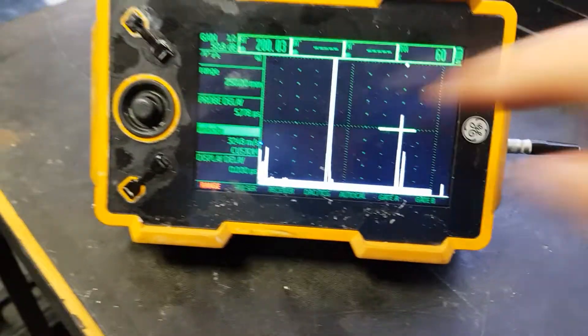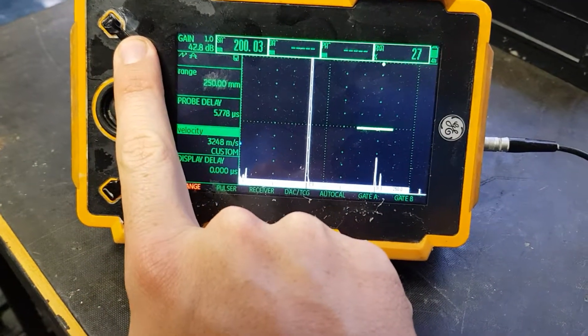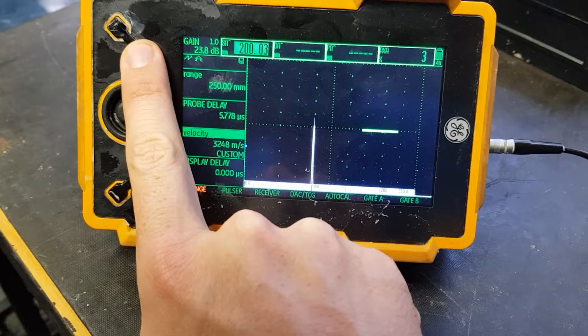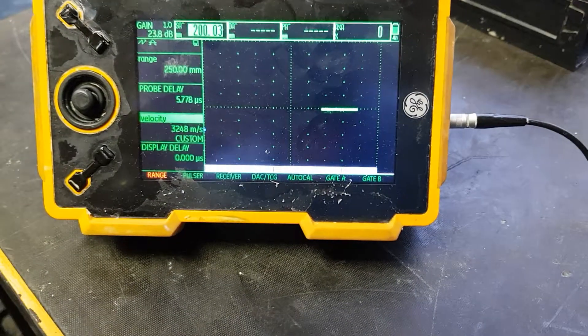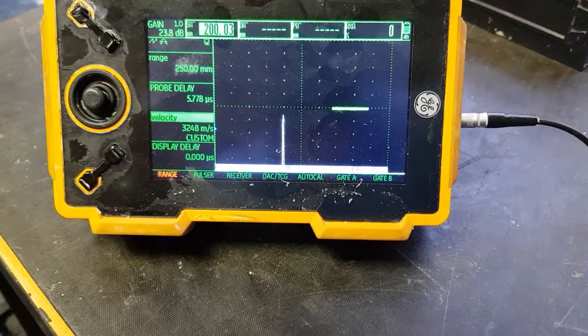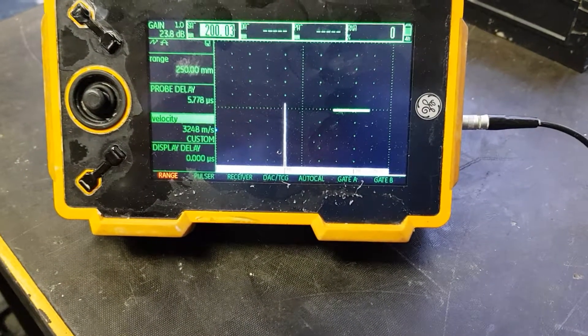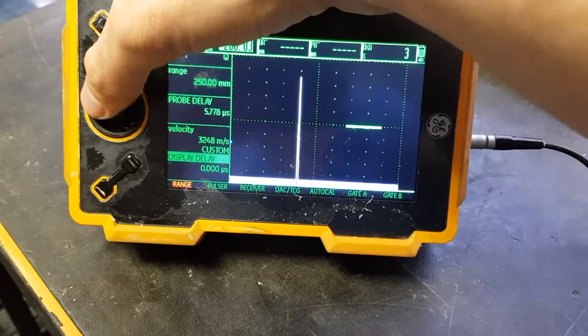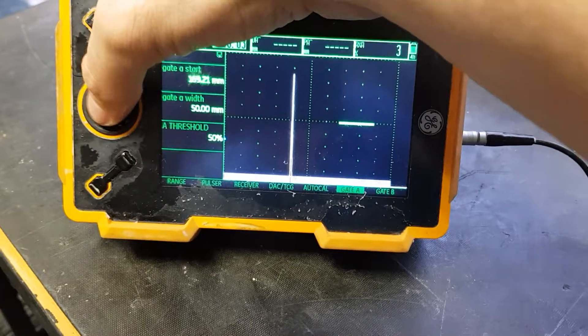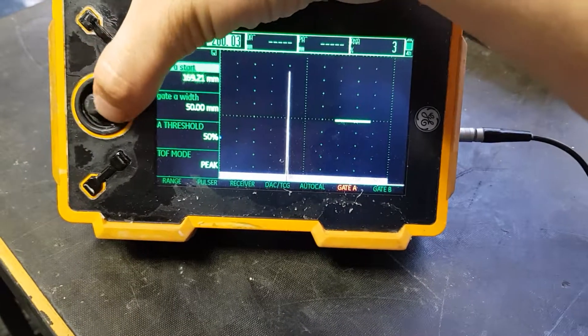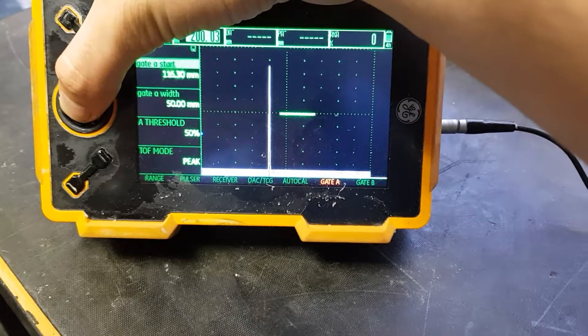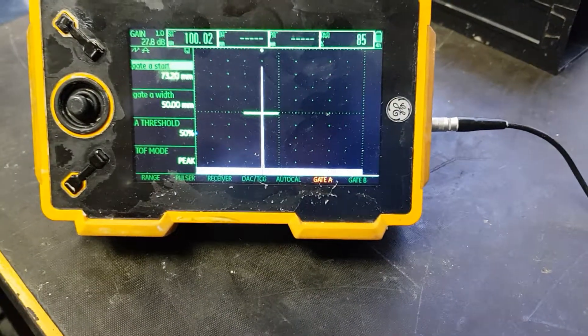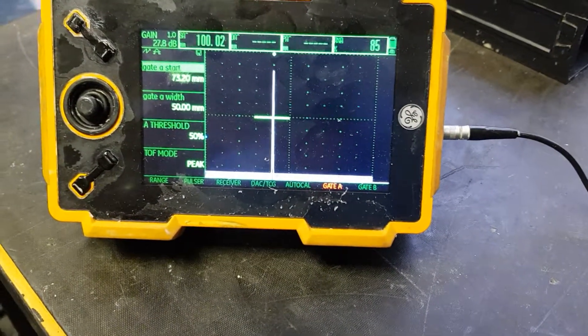Then we go back and lower the dBs again. We maximize the first echo again and move the gate over it. Ensure your gate cuts the echo - if it doesn't, you won't get a reading. If this reads 100, that means it's calibrated.